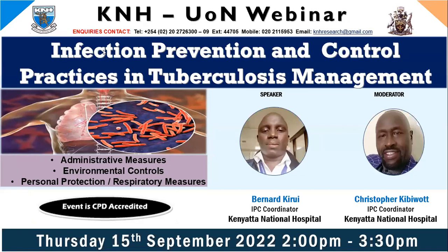So in the ward, we start with endozyme, or what we call enzymatic cleaner. In situations where you don't have enzymatic cleaner, I think we can just go direct to the sodium hypochlorite, but using soap and water would be okay. But now the risk of exposing the person who is doing the cleaning is usually high. So we always recommend the decontamination process to be two-way. Start from the ward by doing the general cleaning and removing the bioburden. Then the next process should go on in the CSSD, or sterilizing unit.